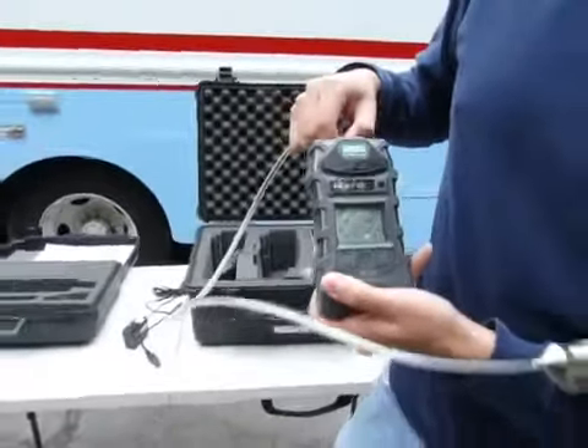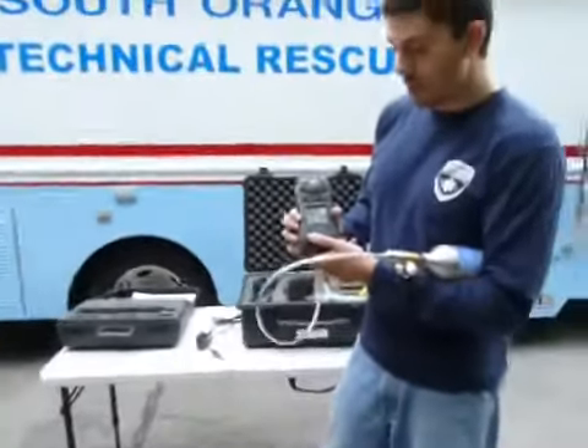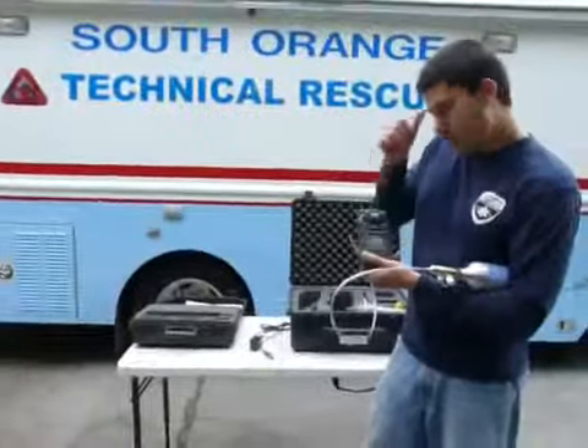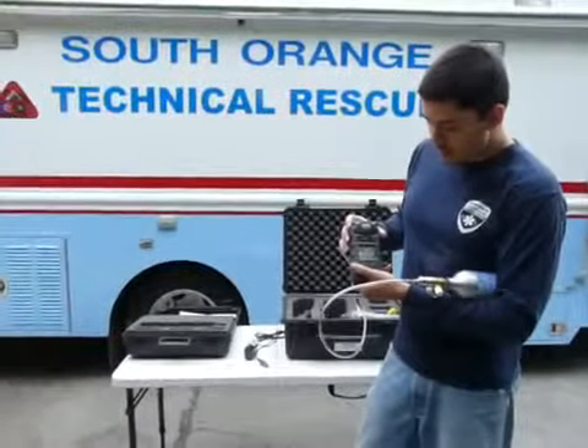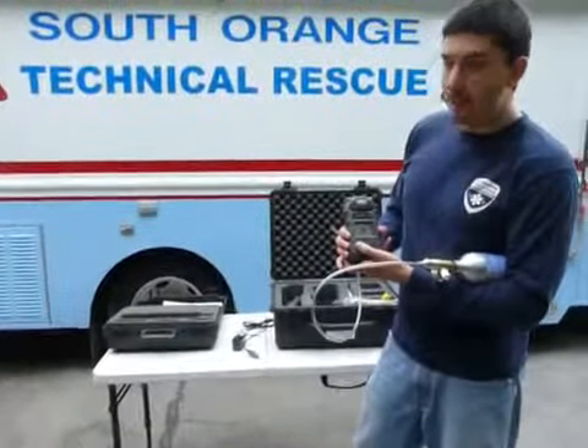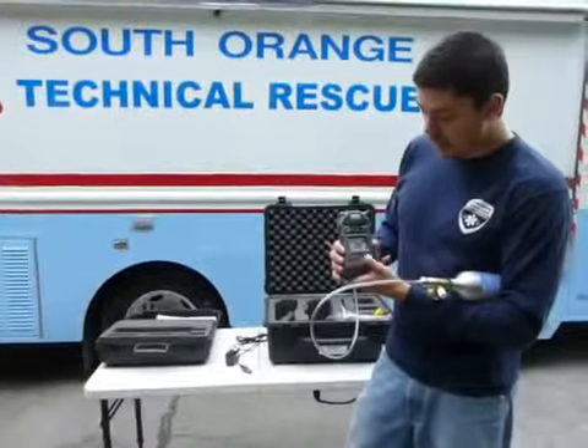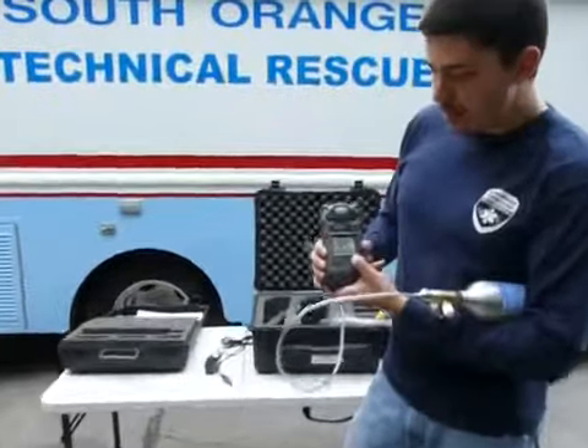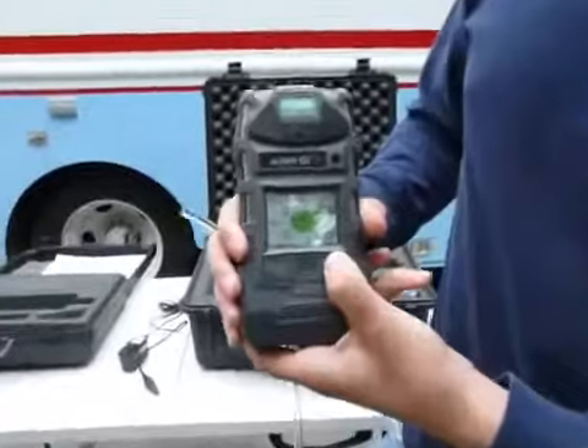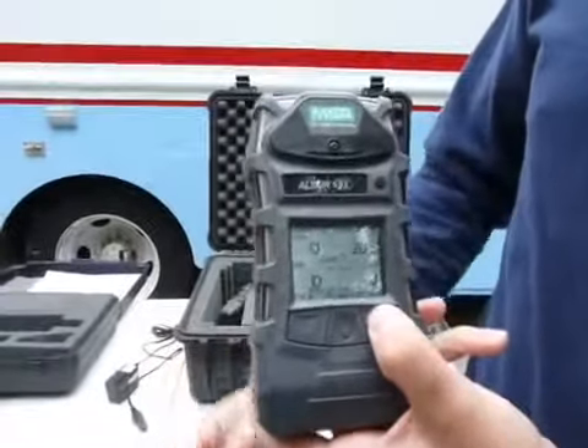And here you can see that each of those sensors passed because they were exposed to that amount of calibration gas. The last thing that we want to go through is how to actually calibrate the unit, and this is important to do once a month. To do this, we're going to push the up button, which says Cal for calibrate.